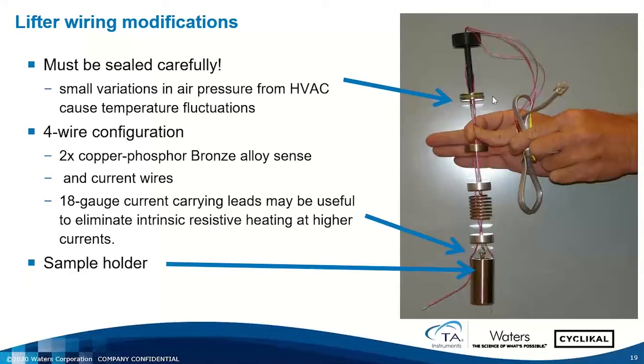This is the most important thermal shunt. We drilled holes in that and then extended our wires down into the sample area. The sample is contained inside of the stainless steel ampule. Importantly, it's critical to seal this particular shunt from any influence that you might see from HVAC equipment. If there's any possibility of airflow through that thermal shunt, the stability of your thermal power signal will be very much compromised.